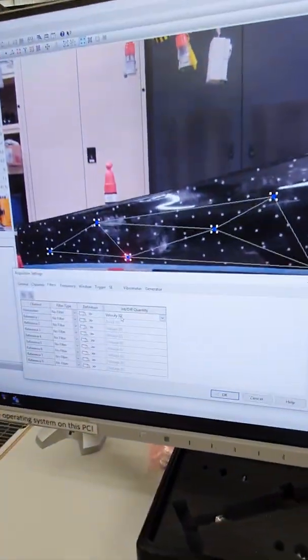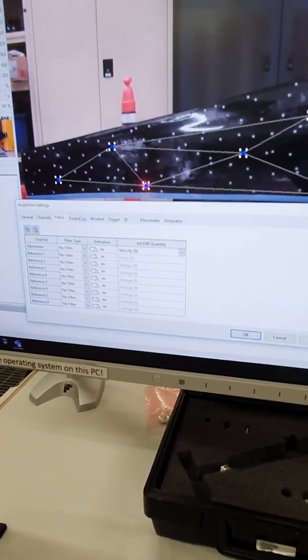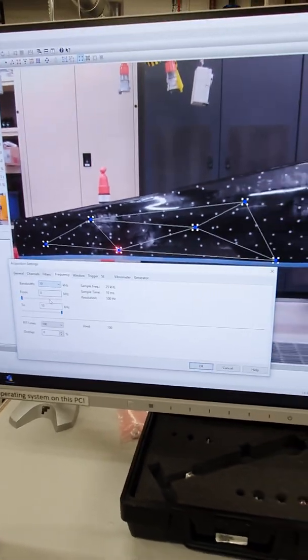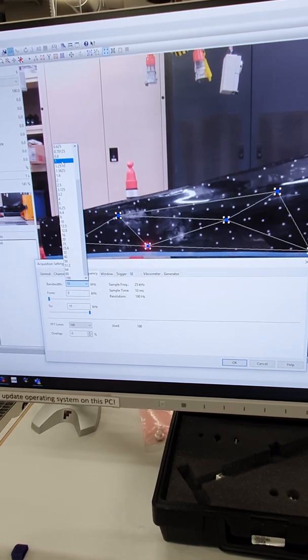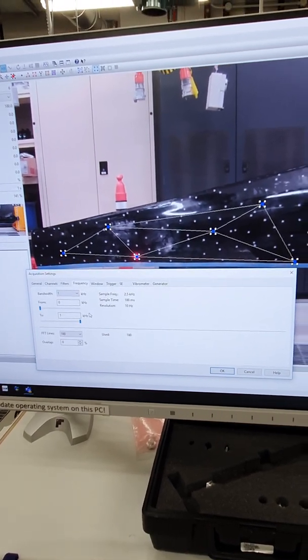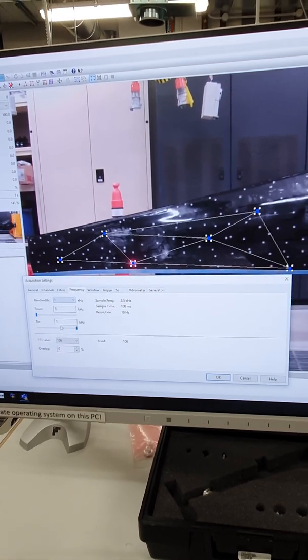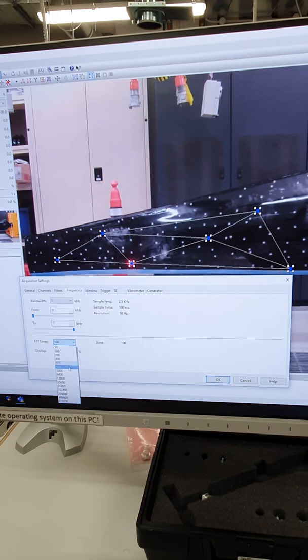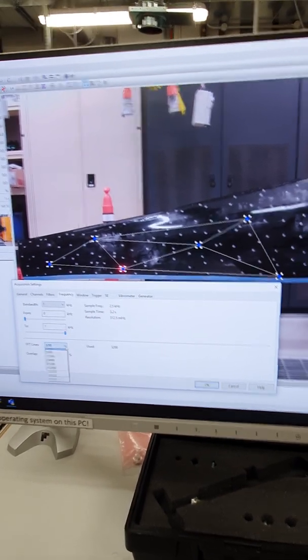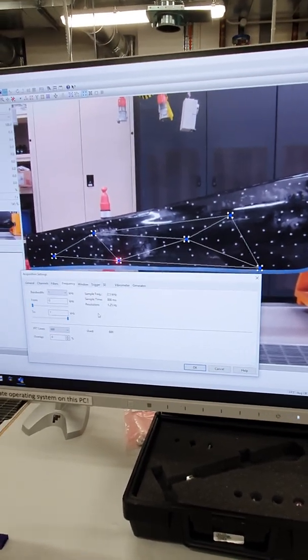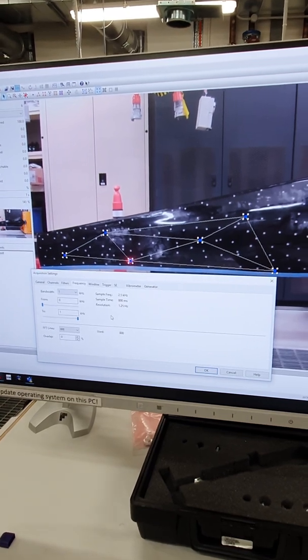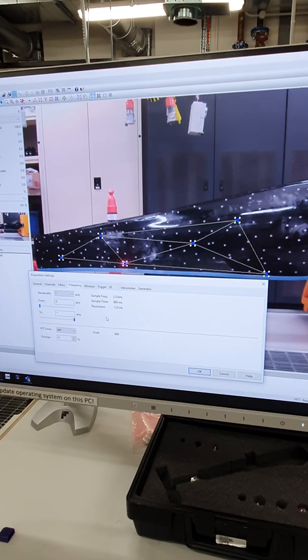I can choose to define some filters: low pass, high pass, band pass filters. We typically try not to use filters, we are interested in all frequency content, but sometimes you might want to implement some filters. I can define the acquisition bandwidth. I mentioned earlier for blades like this, we're probably only interested in the first couple of, three, four natural frequencies, and one kilohertz should be more than enough. The number of spectral lines will define the resolution in the spectrum. The frequencies are reasonably well separated, probably. If we've got a symmetrical structure with two modes very close together, we might want fine spectral resolution.